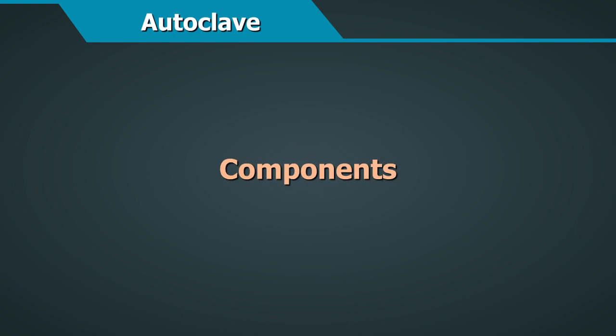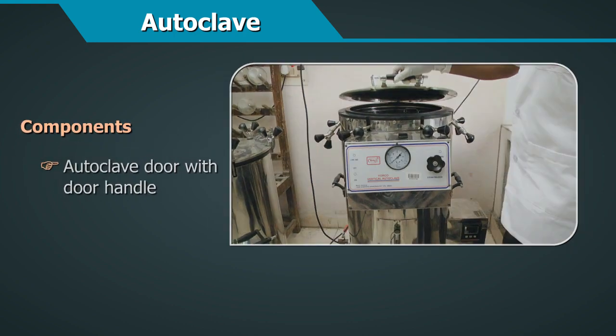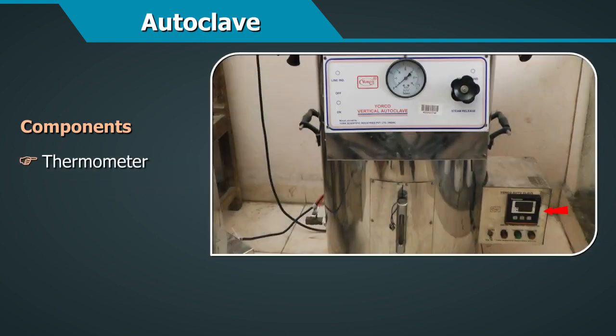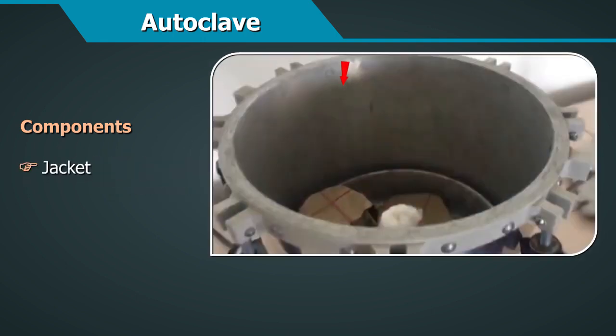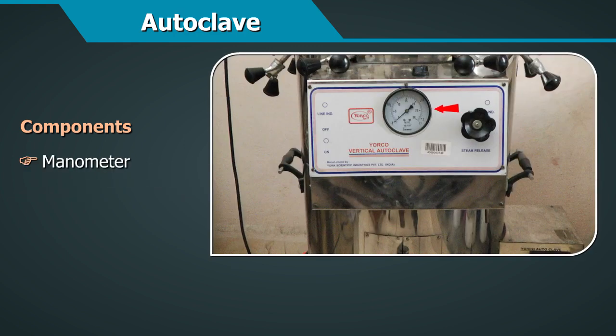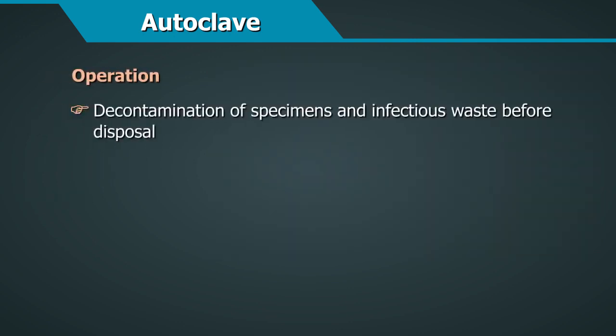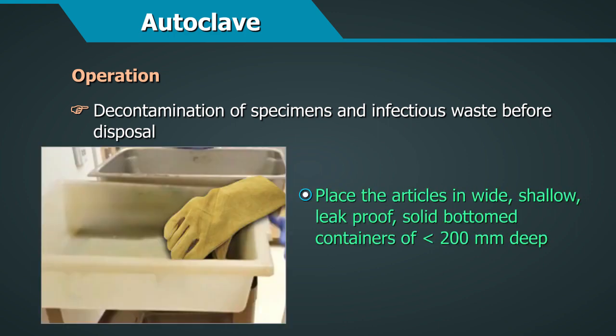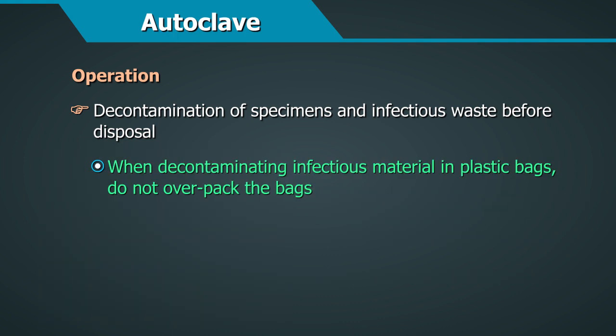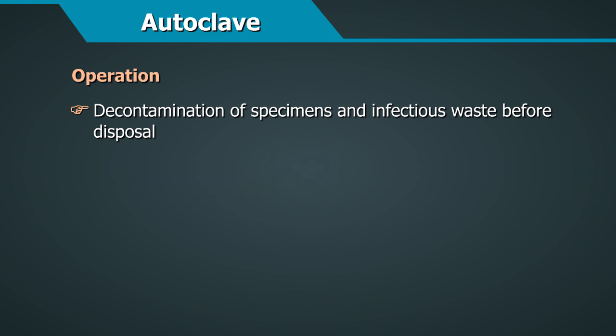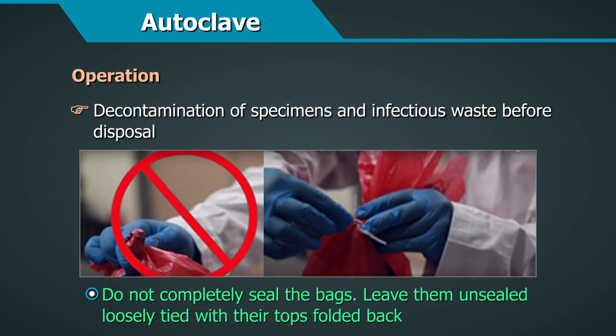Components. The main components of big autoclaves used in large hospitals are autoclave door and lid, sterilization chamber, thermometer, jacket, drain, chamber's manometer, safety valve. Operation: decontamination of specimens and infectious waste. Place the articles for decontamination in wide, shallow, leak-proof, solid-bottomed containers, not more than 200 millimeters deep. Do not cover the containers. When decontaminating infectious material in plastic bags, do not overpack the bags. Leave them unsealed with their tops folded back.